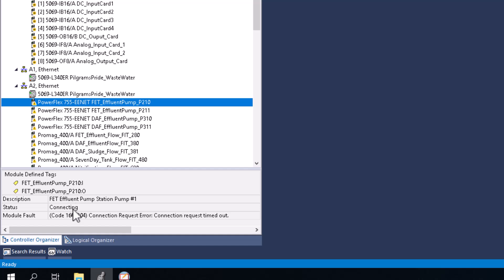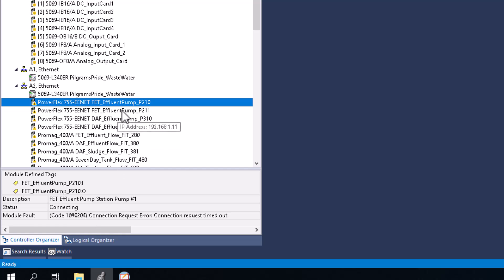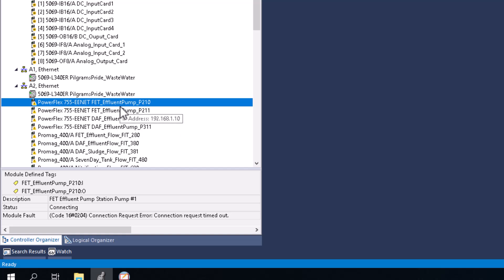the status, what is it trying to do? Is it trying to connect right now? It's trying to connect, but the module fault right now is that the current connection request is an error. So obviously at this point in time, we know where to troubleshoot it. We know to go look at the actual connection or to go look at the switch or to go look at the ethernet cable or to go look at the drive itself.